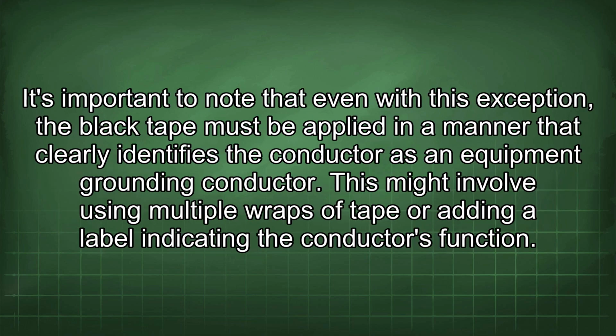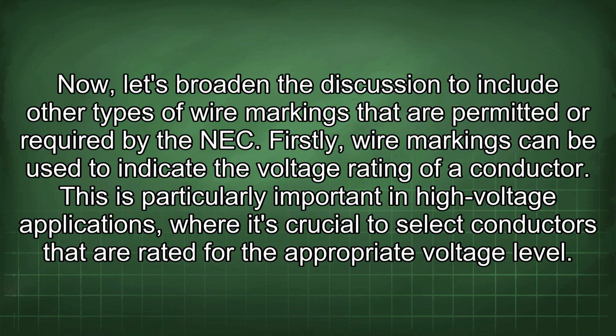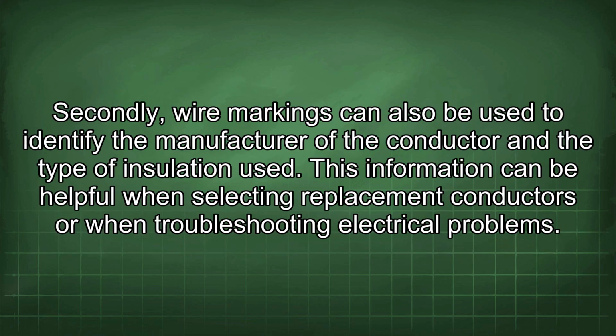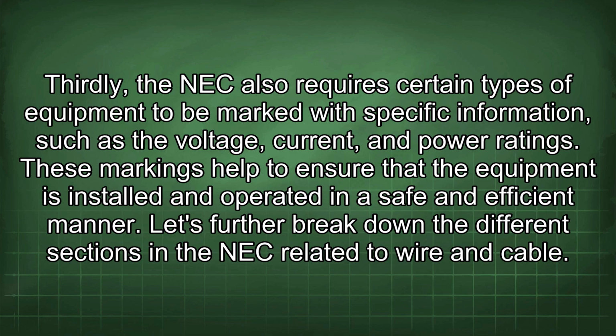It's important to note that even with this exception, the black tape must be applied in a manner that clearly identifies the conductor as an equipment grounding conductor. This might involve using multiple wraps of tape or adding a label indicating the conductor's function. Now let's broaden the discussion to include other types of wire markings that are permitted or required by the NEC. Firstly, wire markings can be used to indicate the voltage rating of a conductor. This is particularly important in high-voltage applications where it's crucial to select conductors that are rated for the appropriate voltage level. Secondly, wire markings can also be used to identify the manufacturer of the conductor and the type of insulation used. This information can be helpful when selecting replacement conductors or when troubleshooting electrical problems. Thirdly, the NEC also requires certain types of equipment to be marked with specific information such as the voltage, current, and power ratings. These markings help to ensure that the equipment is installed and operated in a safe and efficient manner.